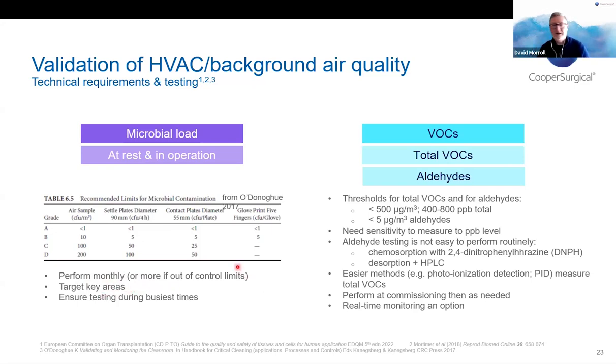The other element that's really critical to embryology labs, of course, is VOCs. And here we have a particular focus on aldehydes, but total VOCs is an easier way of testing. And you're probably aware from the Cairo consensus that less than 500 micrograms per cubic meter, or 400 parts per billion is an easier way to look at it, is the lower threshold for acceptable levels of VOCs. So we need to test to parts per billion level.